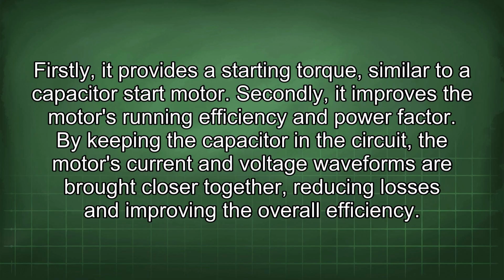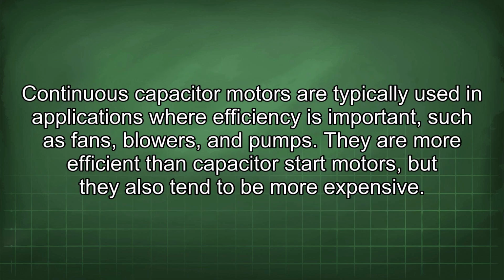improving the overall efficiency. Continuous capacitor motors are typically used in applications where efficiency is important, such as fans, blowers, and pumps. They are more efficient than capacitor start motors, but they also tend to be more expensive.